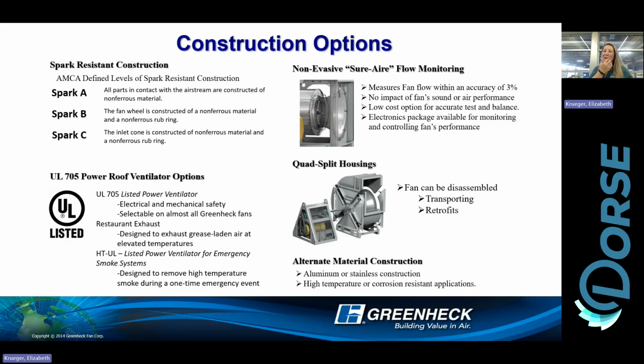Lastly, on this slide, I did want to talk about Sure Air flow monitoring. Flow monitoring is becoming much more common nowadays because everybody wants to modulate their fans based on flow in the system. So if one portion of the system changes to accommodate more air or maybe more cooling, that means the rest of the system has to react equally. Sure Air is a way to measure that airflow without putting probes in the airstream. It will also help when test and balance comes out and says, oh, this fan isn't getting the air we need to the system below.